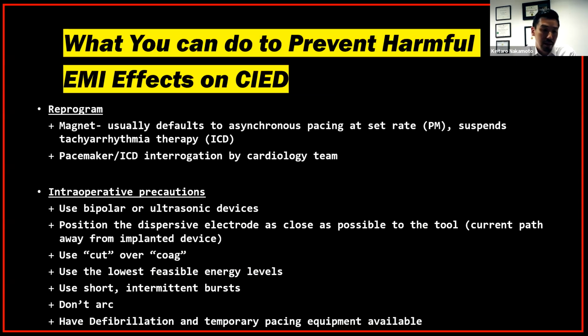Reprogramming can be done in two ways. You can use a magnet, or more formally, ask the cardiologist to do a pacemaker or ICD interrogation. The magnet usually defaults pacemakers to asynchronous pacing at a set rate, and for ICDs, it suspends tachyarrhythmia therapy. The more formal interrogation by the cardiology team usually lets you figure out the exact settings the pacemaker is set at and adjust them accordingly.